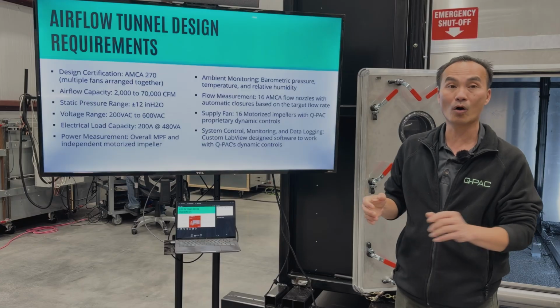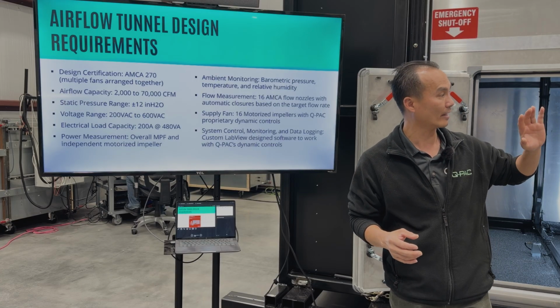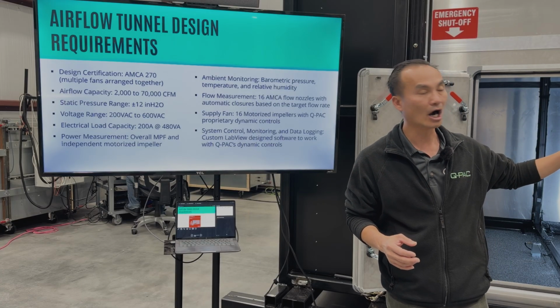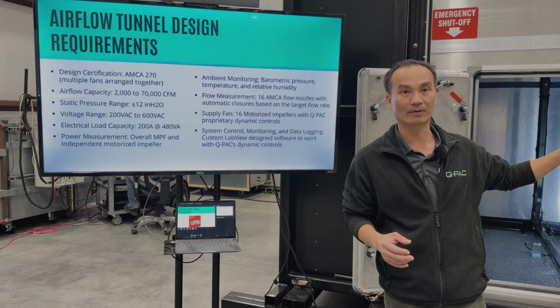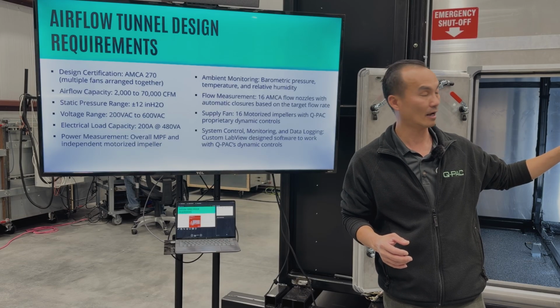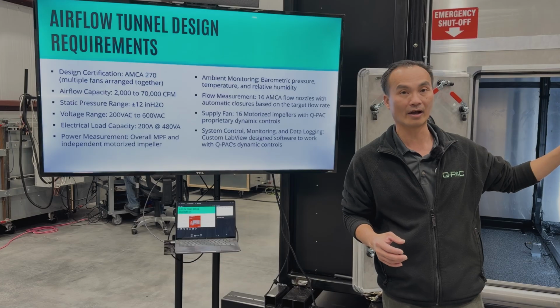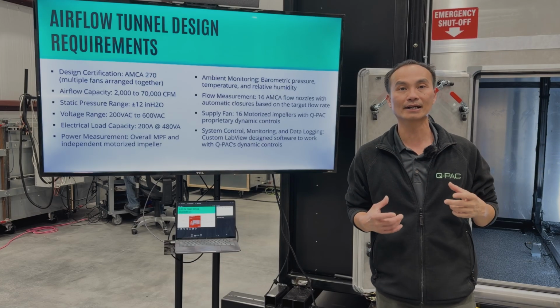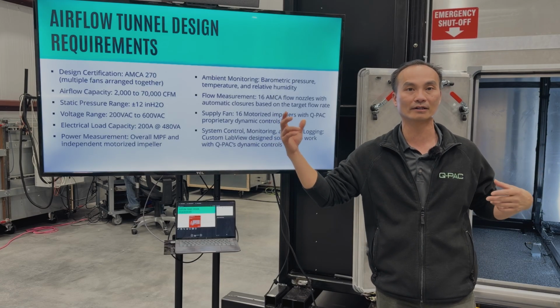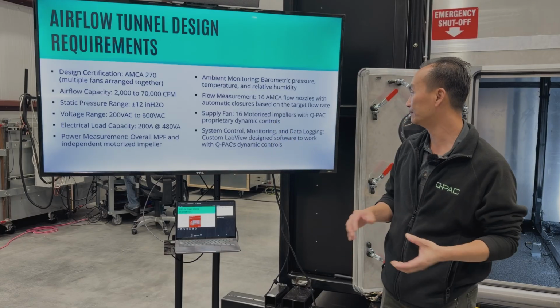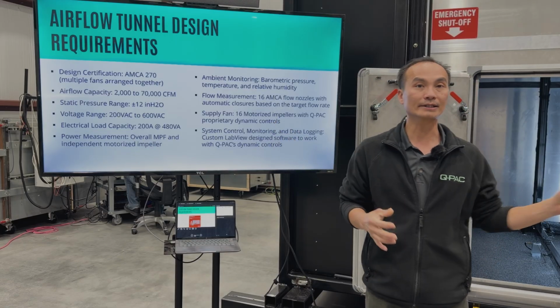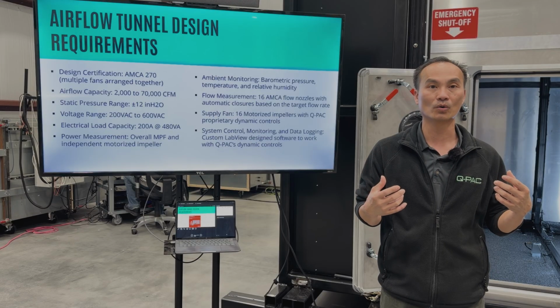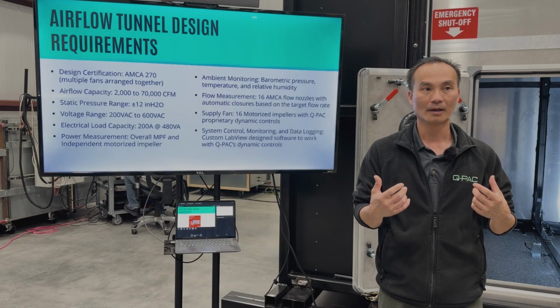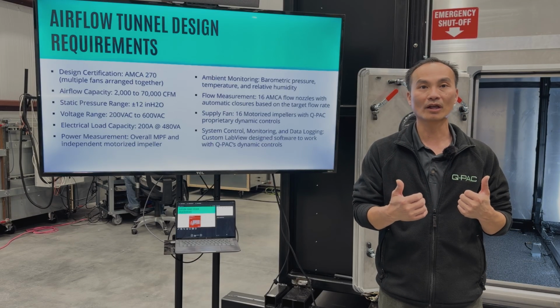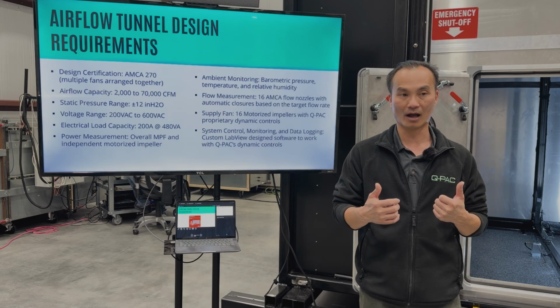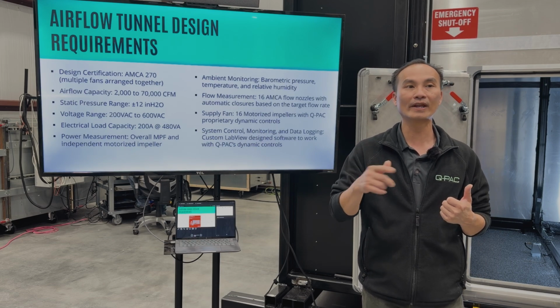Flow measurement, we make custom-made 16 cones, which you probably already saw in the walkthrough of the airflow tunnel. That combined with the 16 fans allows us to test a wide range of testing capability. Again, system control. This system control is not just to control the airflow tunnel and how it works, but it also has built in something very unique, which is machine learning capability to feed the data.